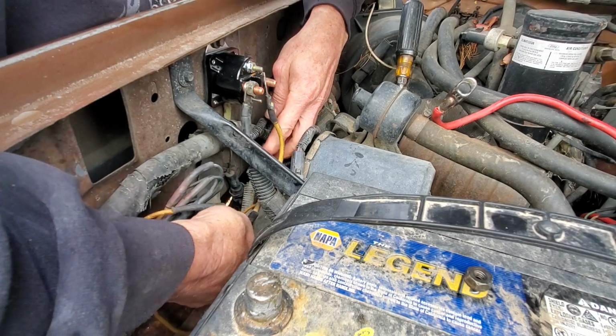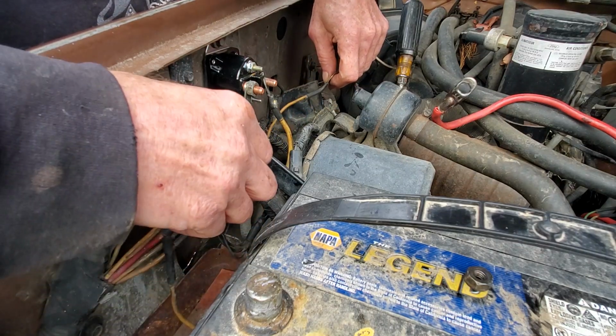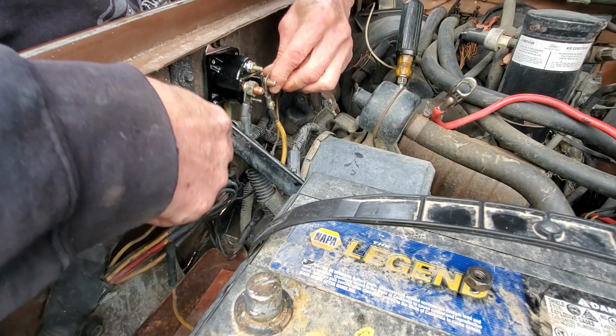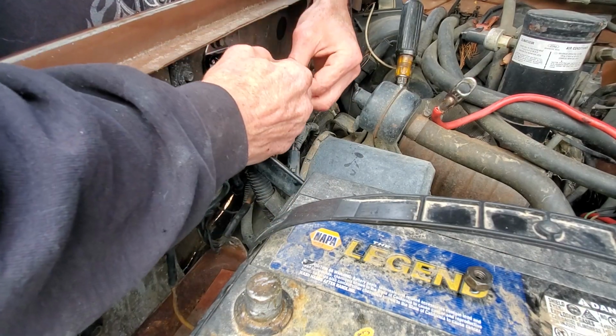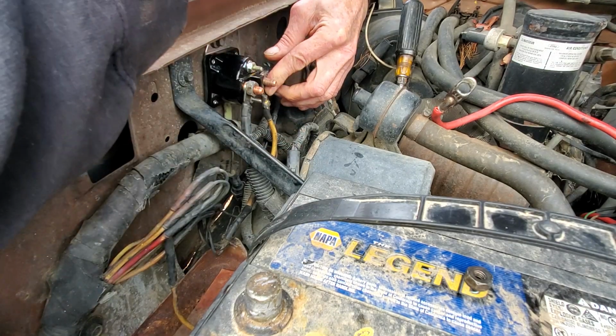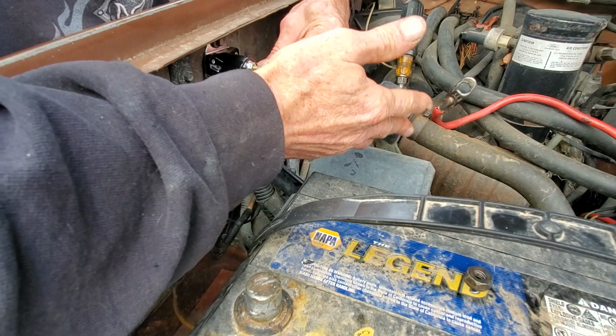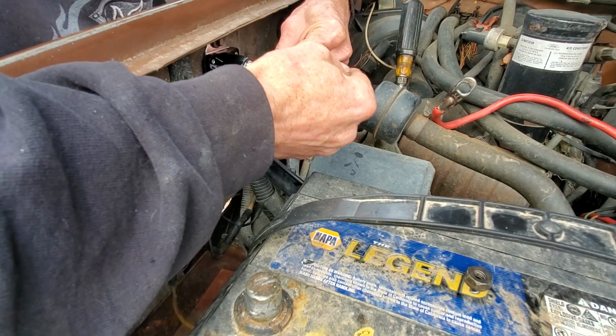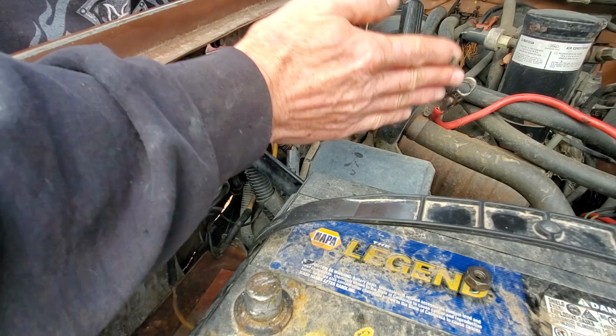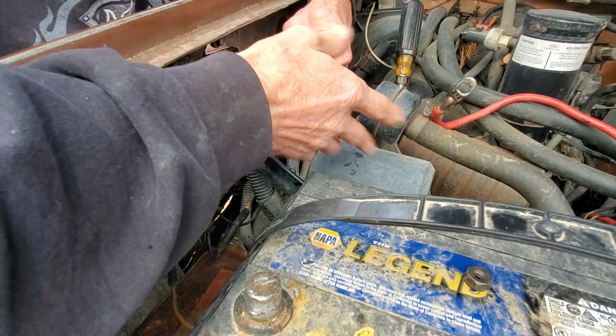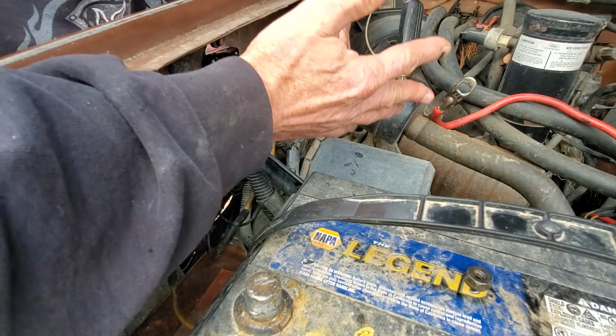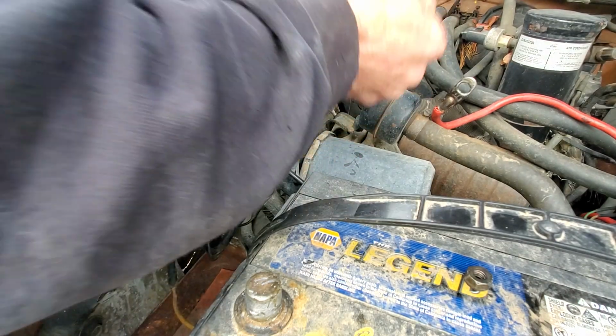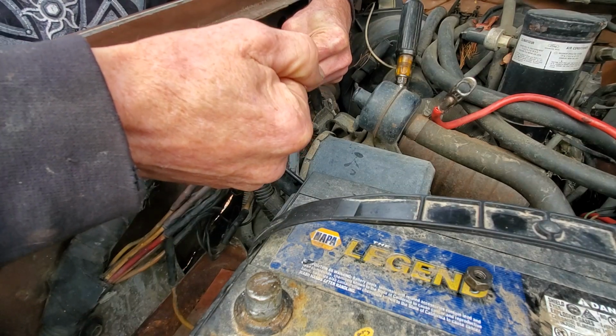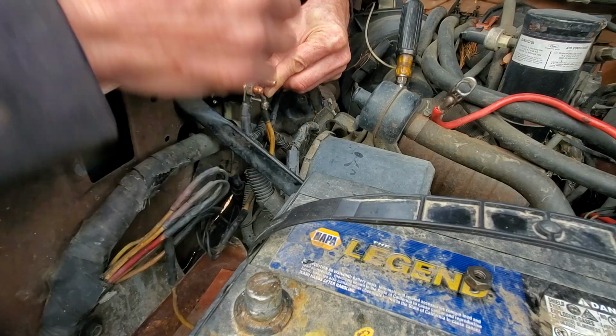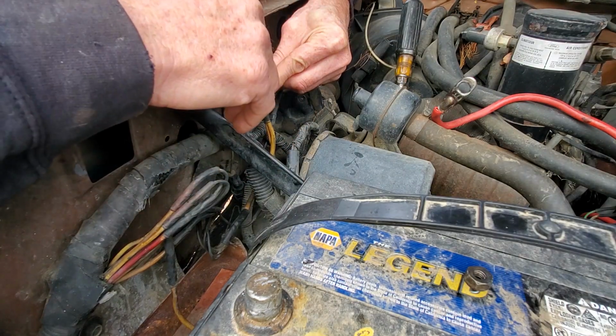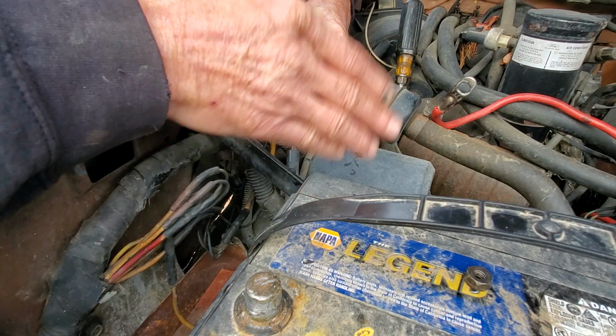There's not too much to say about fuse links other than I want you to understand when you would decide to use a fuse link. You already know when you want to use a circuit breaker — you want something to disconnect power when there's a fault. But what do you do when that wire is drawing different amounts of current depending on what you choose to use in your vehicle, and when those items kick on, how much inrush is that on the overcurrent protection device, like the fuse or the breaker?